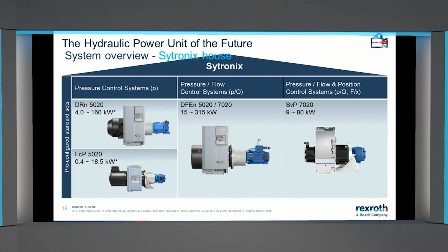Depending on the system, the Sytronix variable speed pump system consists essentially of a drive unit equipped with a frequency converter and control electronics that share the equivalent philosophy of CytroBox and CytroPac, together with a standard or servo motor and hydraulic pump. The flow rate of the hydraulic pump operates proportionally to the drive control of the electrical motor, and the system pressure is measured by the pressure transducer, sending to the servo controller. Based on the control deviation, the built-in PID controller calculates the required motor speed and adapts it accordingly to the existing system requirements of flow rate and pressure.